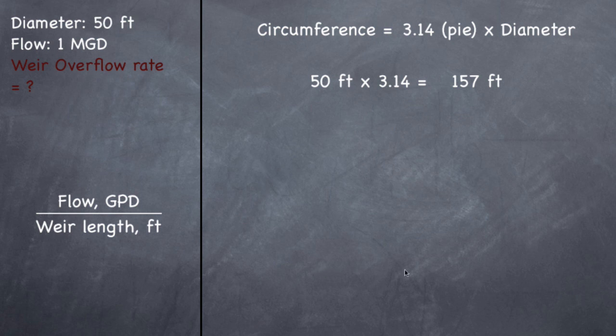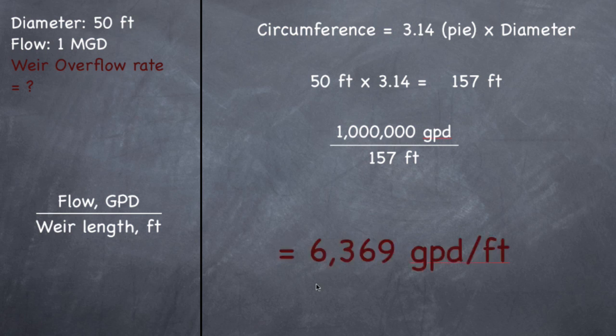So we found the bottom part. So now we need the top part, flow in gallons per day. So they give us the flow in MGD, which is a million gallons per day, but we want gallons per day. So go ahead and multiply one by a million to get a million gallons per day. Divided by 157 feet, which is right all here, this is the formula, should give you 6,369 gallons per day per foot. So one foot of weir in one day will have 6,369 gallons come over it. All right, let's move on.